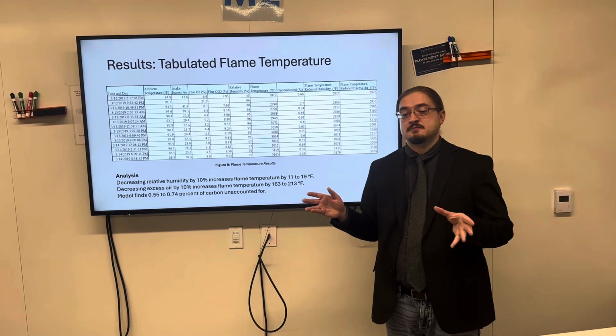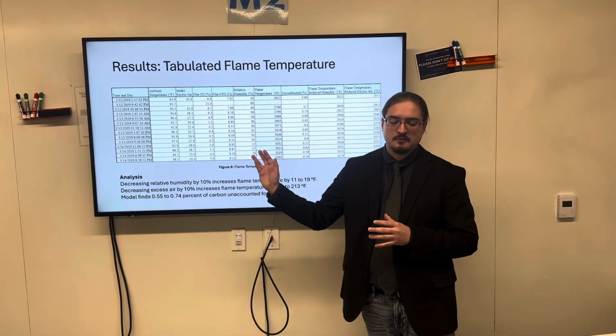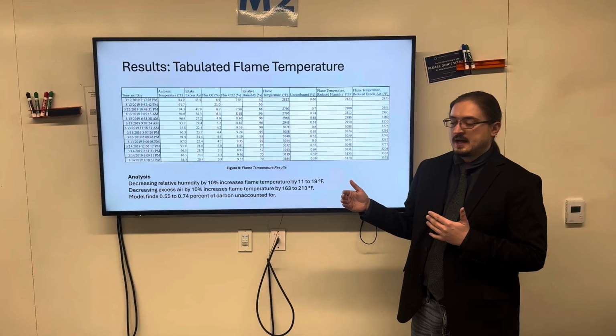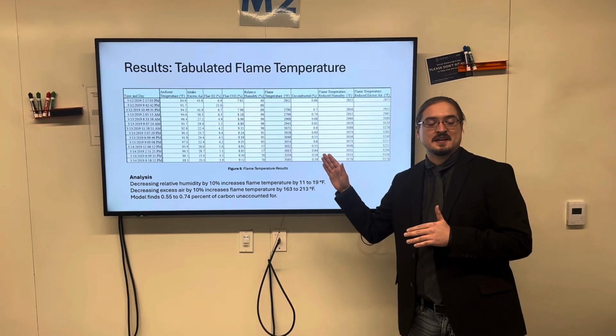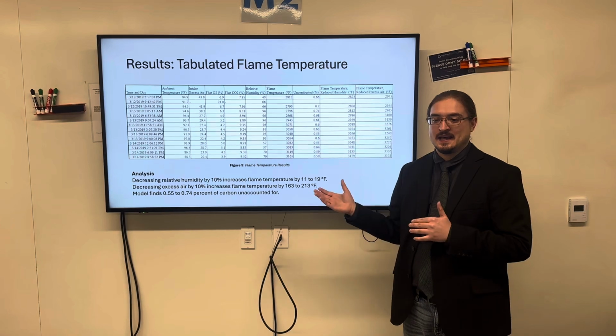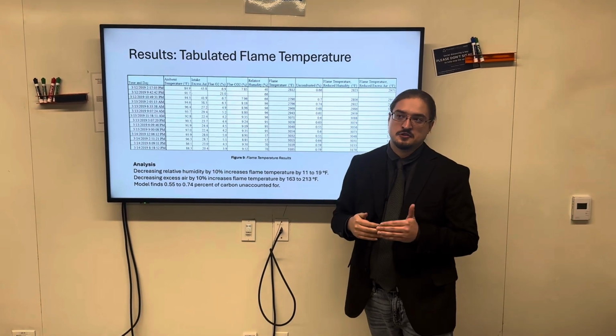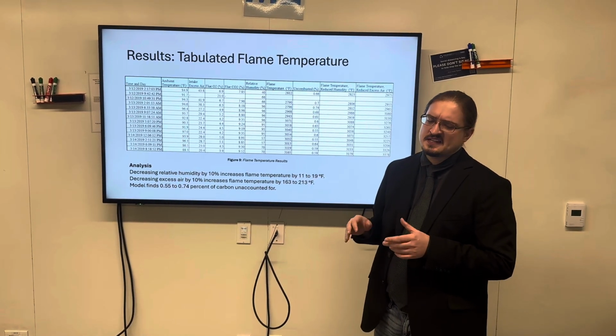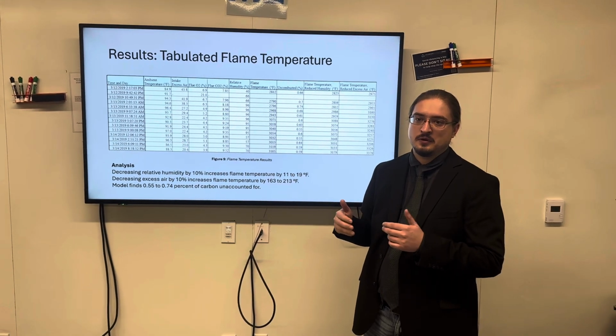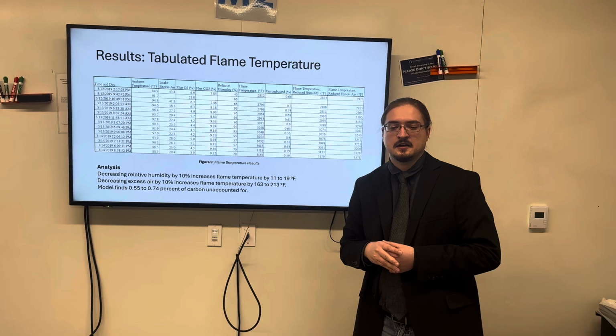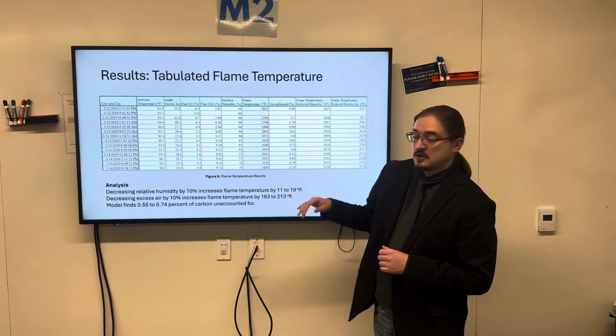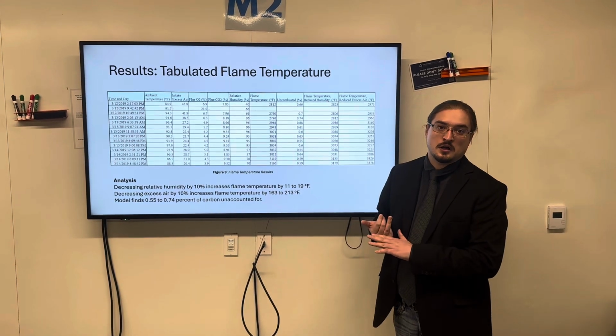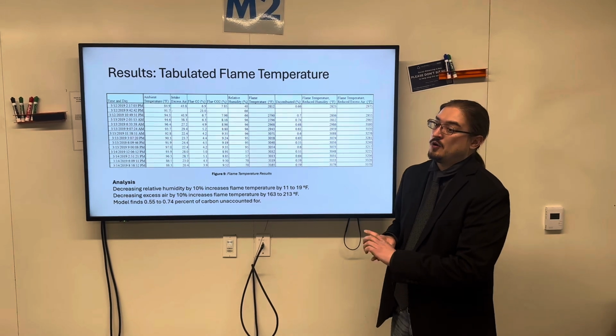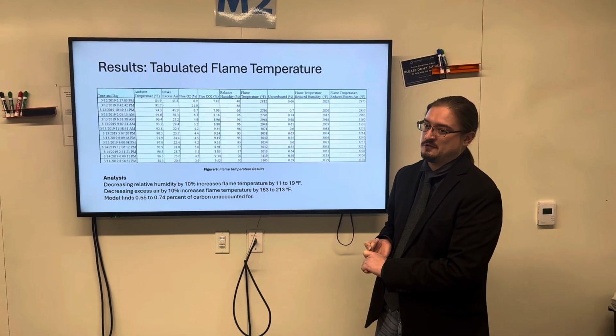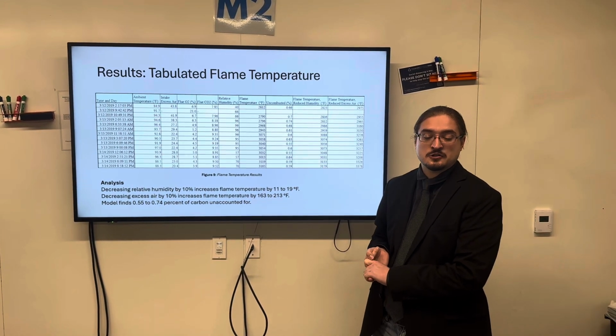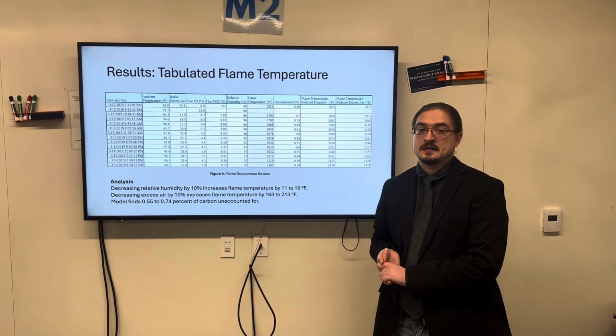Now, while I was running the model, I was curious whether my theoretical calculations would meet the data, and I found that I had around a 0.5 to 0.75% deficit in carbon at the end, as in the data for the CO2 and tiny amounts of carbon monoxide did not add up to the total amount of carbon inputted via the ambient carbon dioxide in the air and the fuel. So that can either mean that the model was wrong, the sensors are not calibrated right, or we might potentially have a very minor fuel leak. It's most likely a model issue, but without further data, I cannot determine that at this time.